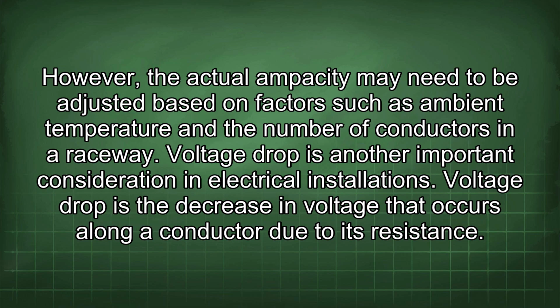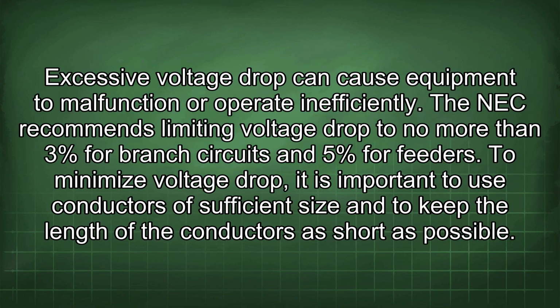conductors in a raceway. Voltage drop is another important consideration in electrical installations. Voltage drop is the decrease in voltage that occurs along a conductor due to its resistance. Excessive voltage drop can cause equipment to malfunction or operate inefficiently. The NEC recommends limiting voltage drop to no more than 3% for branch circuits and 5% for feeders. To minimize voltage drop, it is important to use conductors of sufficient size and to keep the length of the conductors as short as possible.